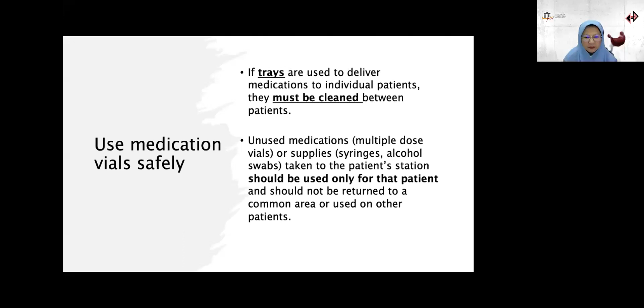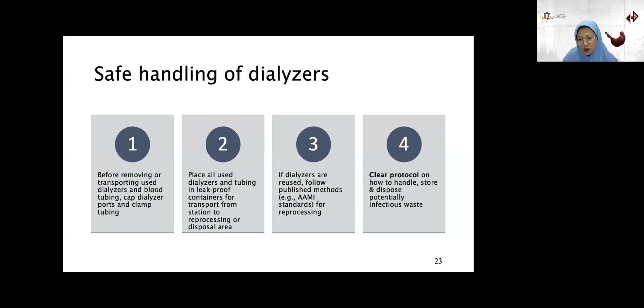Okay, next section is on safe handling of dialyzers. Before removing or transporting used dialyzers and blood tubing, you must cap the dialyzer port and clamp the tubing. Place all used dialyzers and tubing in leak-proof containers for transport from the station to reprocessing or disposal areas. My unit tends to put them in a yellow plastic bag and tie it off before transportation. If dialyzers are reused, follow published methods such as the AAMI standard for reprocessing and a clear protocol on how to handle, store, and dispose of potentially infectious waste.